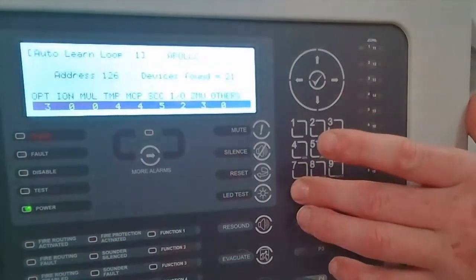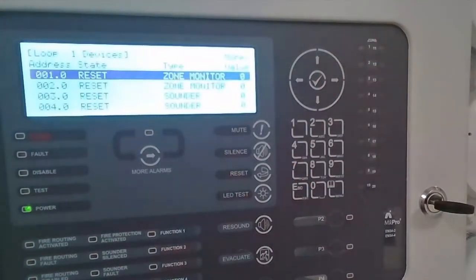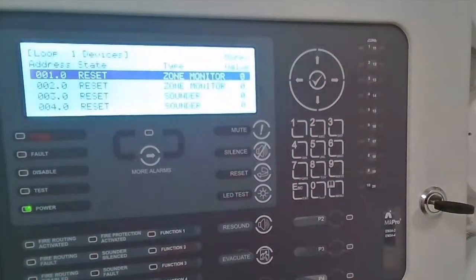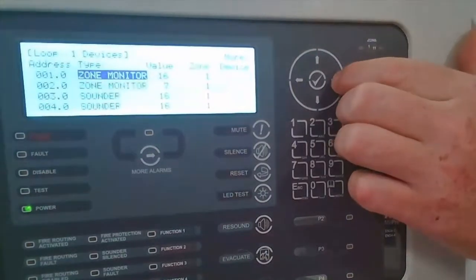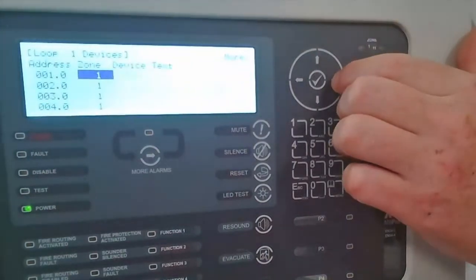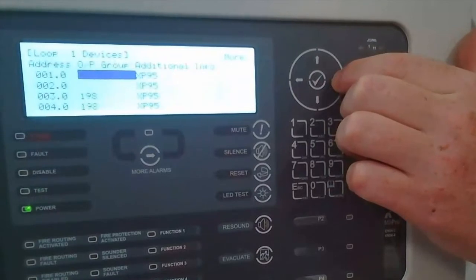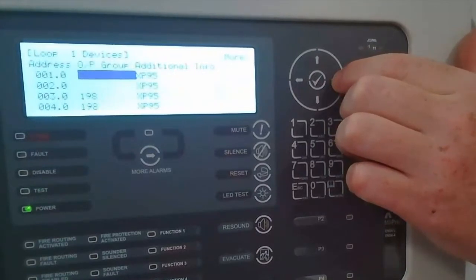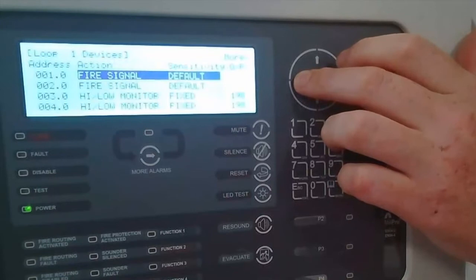If I escape and then select the view and edit option. The devices are just coming online so they're still in reset mode — they'll slowly change to normal. If we scroll to the right for more information, they are reporting as the standard XP95 devices. The panel does not know they are the EMS FireCell wireless type devices.